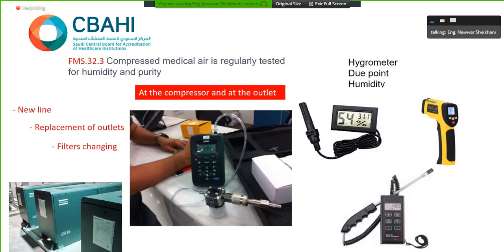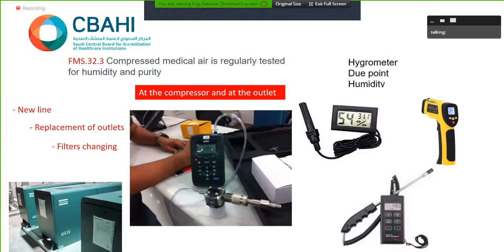So how to control it? It's very difficult to control. I cannot ask the hospital, okay, give me the date you installed a new line, and based on it we check your testing of humidity and purity, or when you replaced the outlet, or give me the date you changed the filter. It's complicated. So that's why we have agreed with our colleagues in hospitals and in CBAHI surveys as well, let's make it quarterly to make sure that hospitals are doing it. And it's easy, by the way.